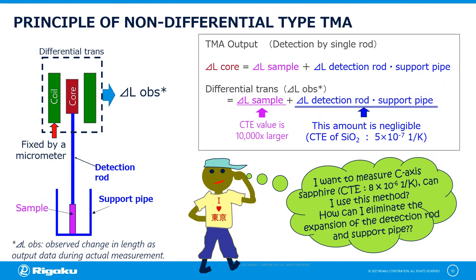The non-differential type TMA, or generally termed as single rod TMA, is suitable for polymers or materials with large thermal expansion. In this system, when heated, the support pipe, the detection rod, and the sample length change. Therefore, the output data or delta L observed will be equivalent to the change in length of the sample, the detection rod, and the support pipe. Since the CTE value of polymers is 10,000 times larger than the expansion of the detection rod and support pipe, the CTE value of the detection rod and the support pipe becomes negligible.